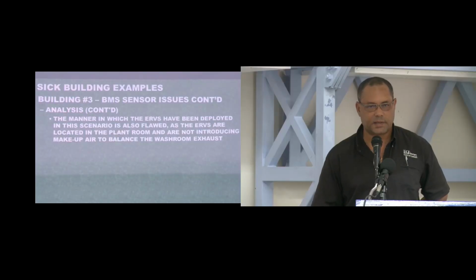And beyond preventing it from working properly, the ERVs are designed to exhaust a space that needs to be exhausted and bring air back into the building. In this case, they put the ERVs in the plant room. So the air that they are exhausting is not contaminated air. It's actually the return air to the system. So it's not actually changing the amount of air in the building. It's just circulating air. Meanwhile, our exhaust fans are pulling air out.